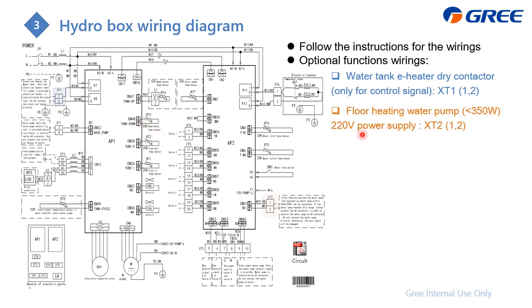And the other is the floor heating water pump, the water pump. If it is less than 350 watt, you can connect to here directly. It is 220 volts power supply. If higher than this value, you need to connect to a dry contactor.